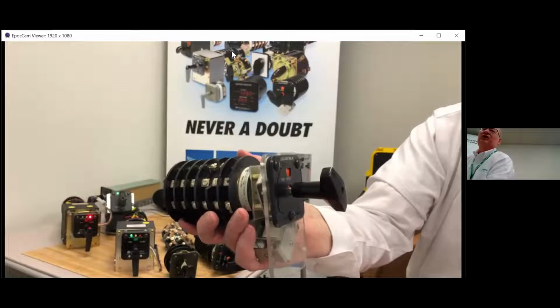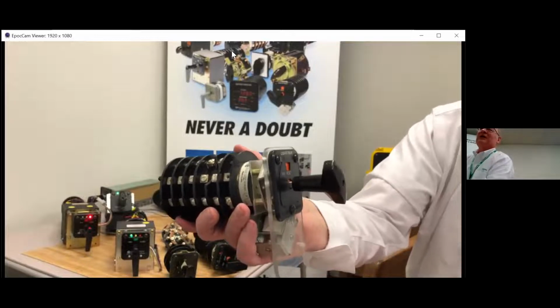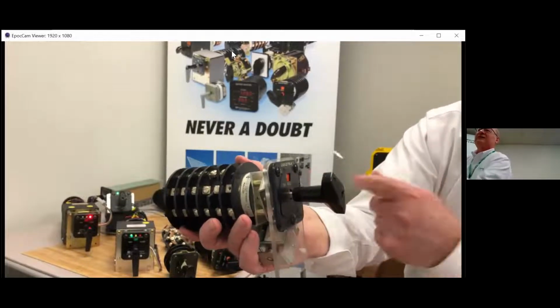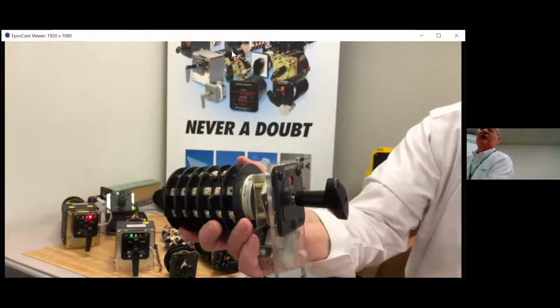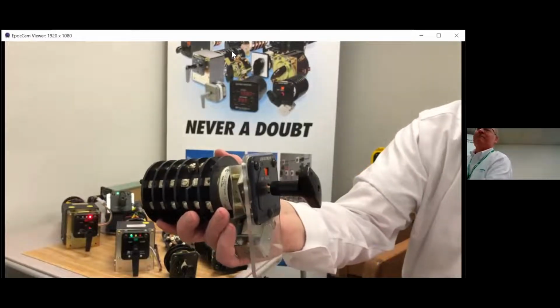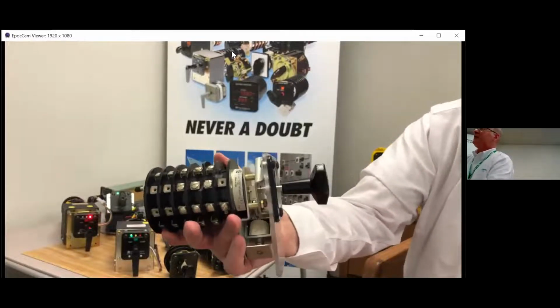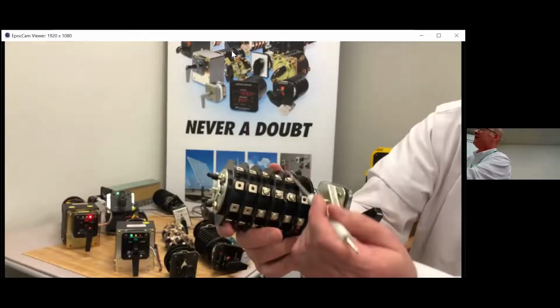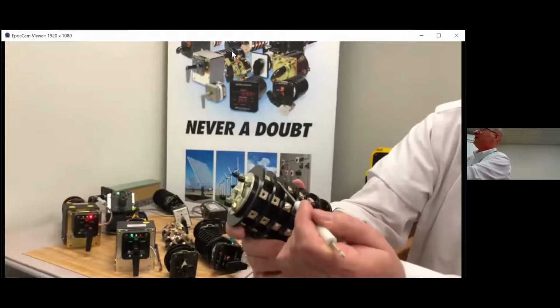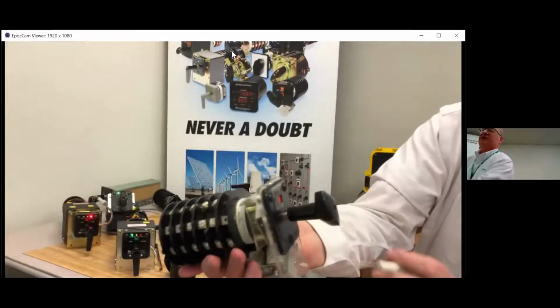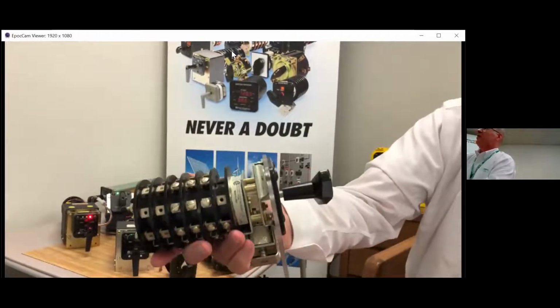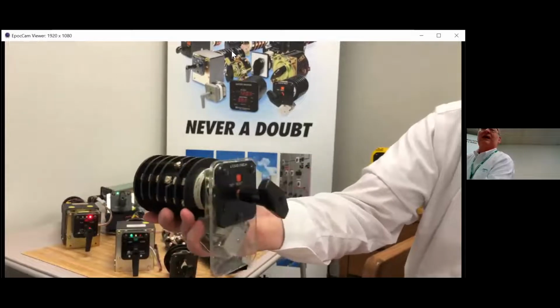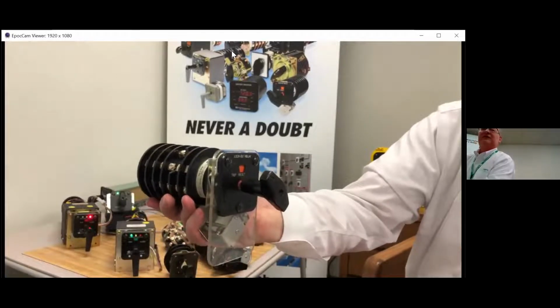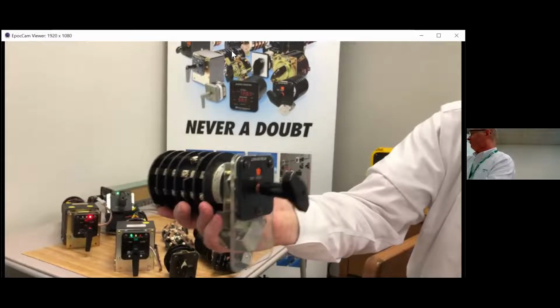This essentially is your insurance policy to make sure that no other circuit is operating until you've gone out and identified the problem. And in this particular case, now you can see this happens to be a 1, 2, 3, 4, 5 deck switch with the control deck for this solenoid. So that's a basic mechanical lockout relay, the 86 function in a substation.